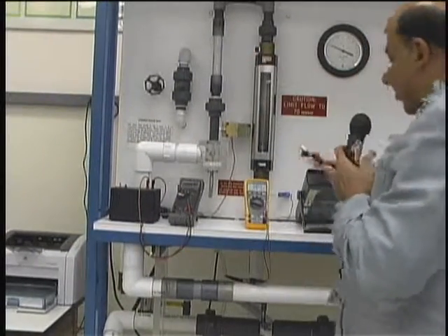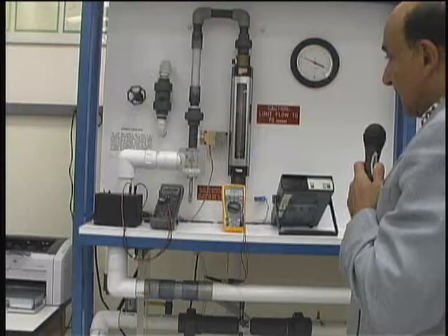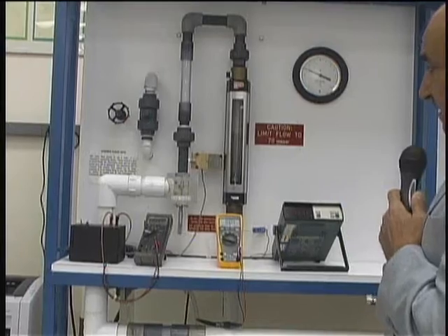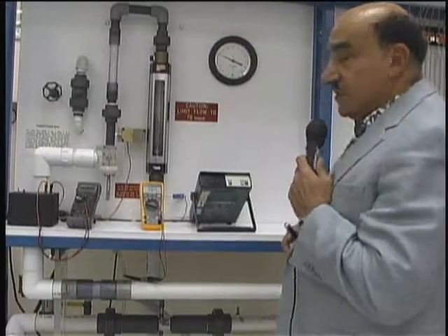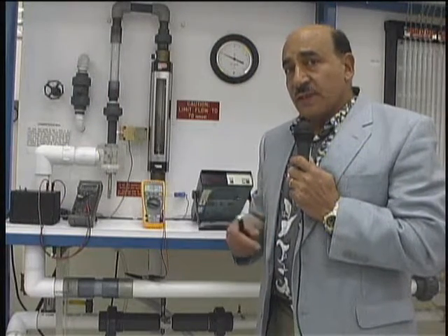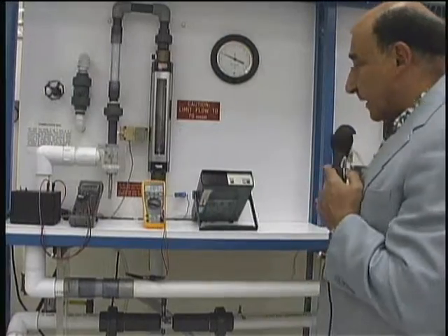Then this continues in series to flow through this rotameter, and the rotameter is graduated linearly, as I mentioned in my lecture, from 0 to 100%. When it's 100%, you get 19.8 cubic feet per minute. So this is calibrated by the manufacturer. And we have the temperature also measured. So this is a thermometer. It's connected to the base of the rotameter, and it gives us the temperature of the air, because we're going to use standard equations for them. We're going to use standard equations related to the mass of the air and its conditions as an ideal gas to make correction for the temperature and the pressure here on the rotameter.